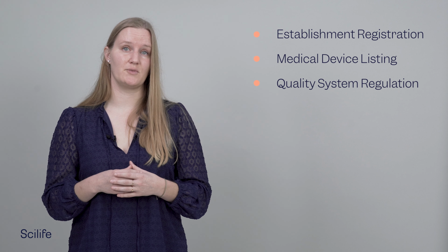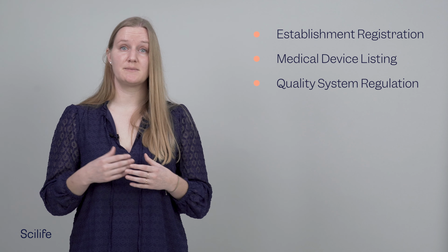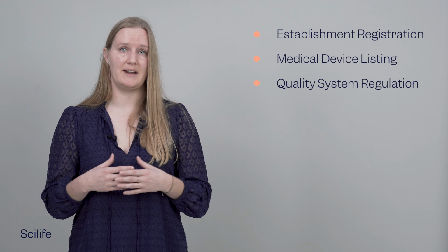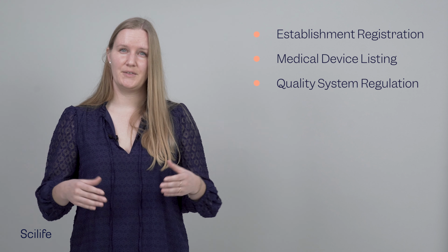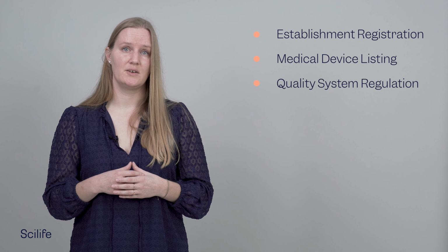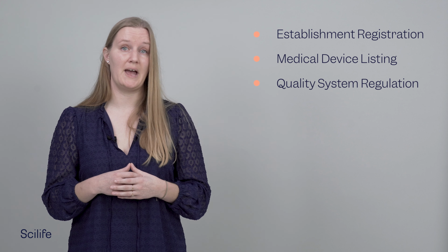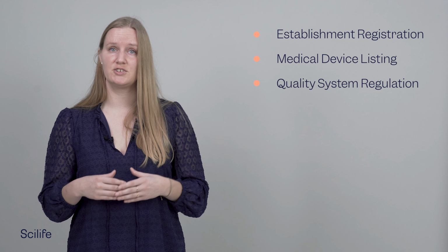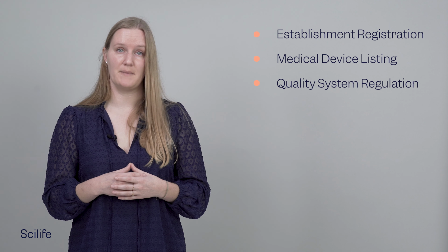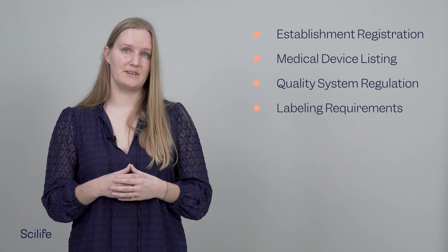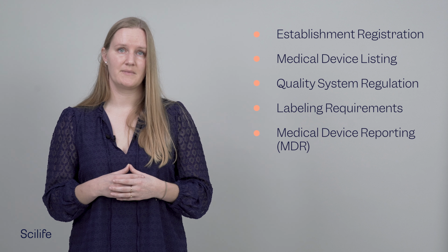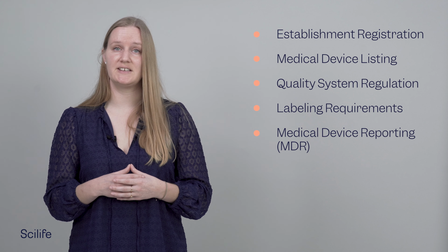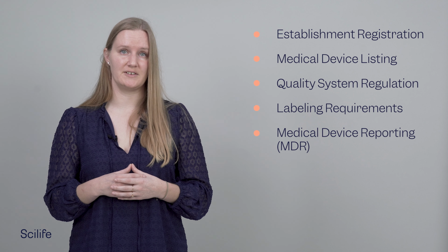The quality system regulation. Manufacturers must design and implement a quality management system, or QMS, before pre-market submission. This system should include requirements related to the methods used in the design, purchase, manufacture, packaging, labeling, storage, controls, and servicing of medical devices. The labeling requirements. The medical device reporting, MDR. The collection of incidents reported to the FDA that will help monitor adverse events.